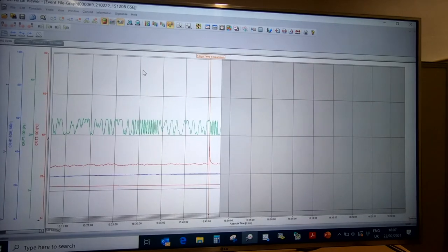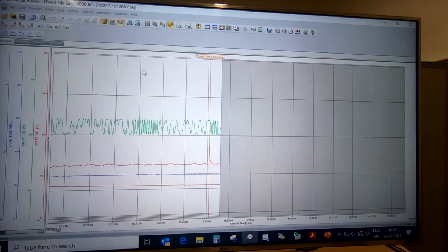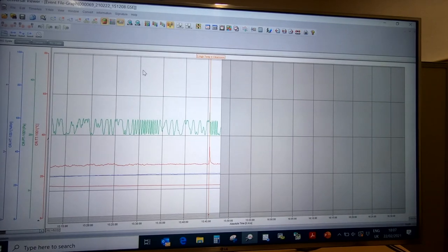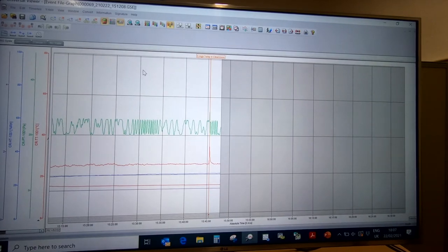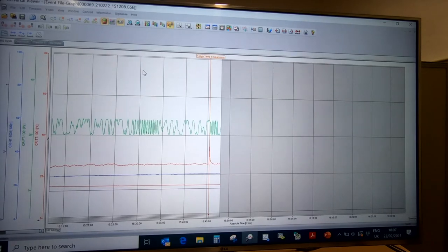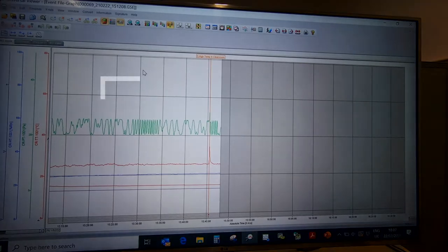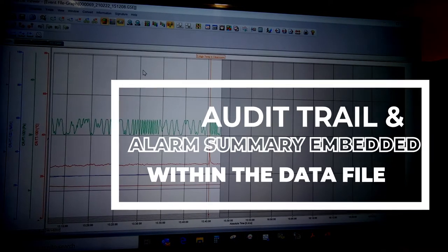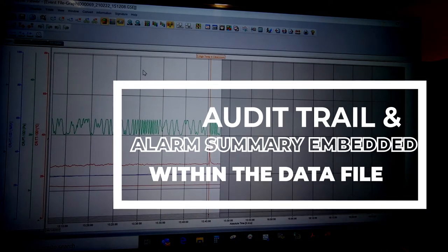When we talk about the software and the data files in terms of data integrity, one of the important things to emphasize is that every data file generated on the Yokogawa SMARTDAC+ series has the audit trail and the alarm summary embedded within the data file.